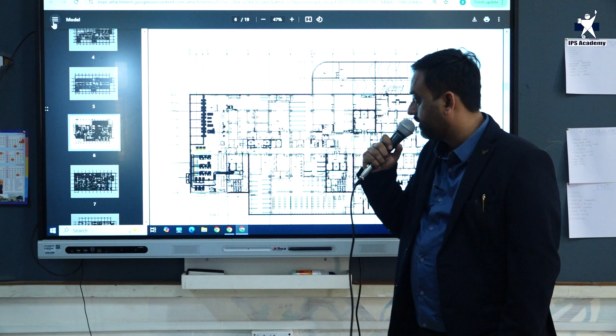So you've seen 2 basements in the Vishesh Hospital project as well. Most of the areas related to radioactive zones, where radiation levels are higher, are planned in the basement with higher thickness walls so that radiation is not emitted to patients or their attenders. In basement 2, we had planned the linear accelerator for cancer treatment. The LINAC bunker has a size of about 900 to 1000 square feet, with a console connected to the radiation equipment area.